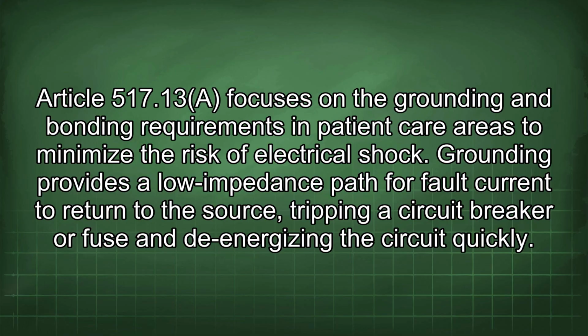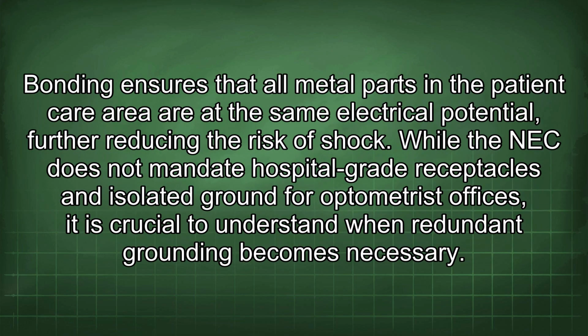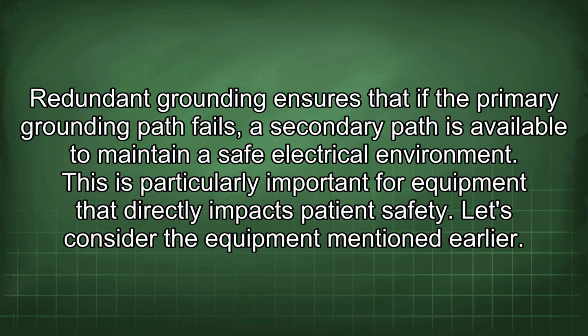Grounding provides a low impedance path for fault current to return to the source, tripping a circuit breaker or fuse and de-energizing the circuit quickly. Bonding ensures that all metal parts in the patient care area are at the same electrical potential, further reducing the risk of shock. While the NEC does not mandate hospital-grade receptacles and isolated ground for optometrist offices, it is crucial to understand when redundant grounding becomes necessary. Redundant grounding ensures that if the primary grounding path fails, a secondary path is available to maintain a safe electrical environment. This is particularly important for equipment that directly impacts patient safety.